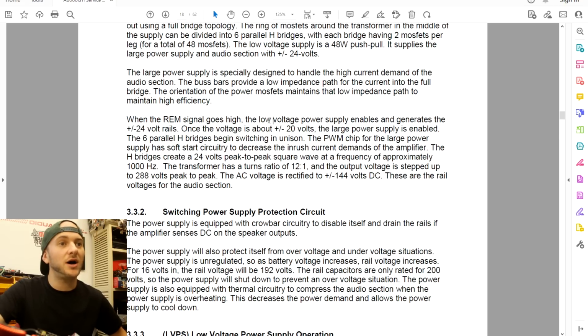It says when the remote signal goes high, the low voltage power supply enables. So there's a separate low voltage power supply in this board that activates first, and then the main plus minus 150 volt power supply enables. First we get plus minus 24 volts, and once the voltage is at about plus minus 20, the large power supply is enabled. That's interesting if you're troubleshooting power supply issues.